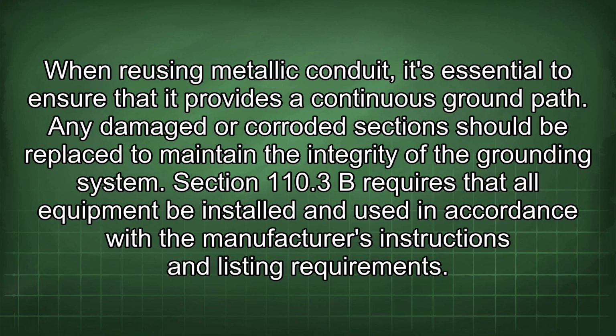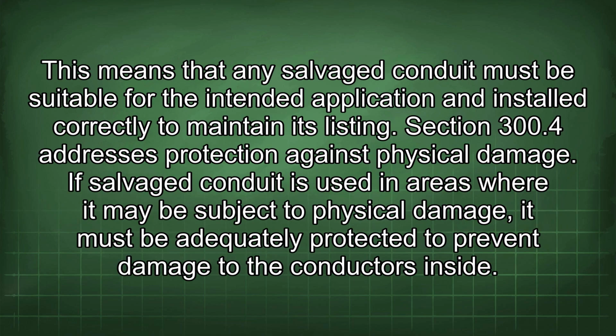Section 110.3(B) requires that all equipment be installed and used in accordance with the manufacturer's instructions and listing requirements. This means that any salvaged conduit must be suitable for the intended application and installed correctly to maintain its listing. Section 300.4 addresses protection against physical damage. If salvaged conduit is used in areas where it may be subject to physical damage, it must be adequately protected to prevent damage to the conductors inside.